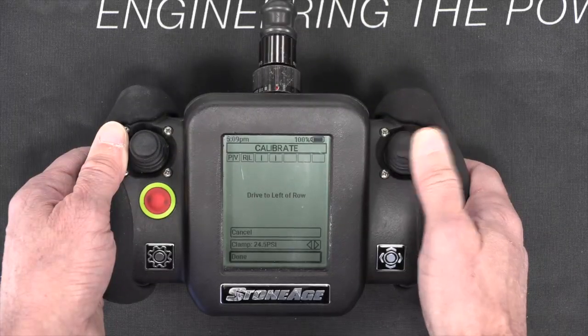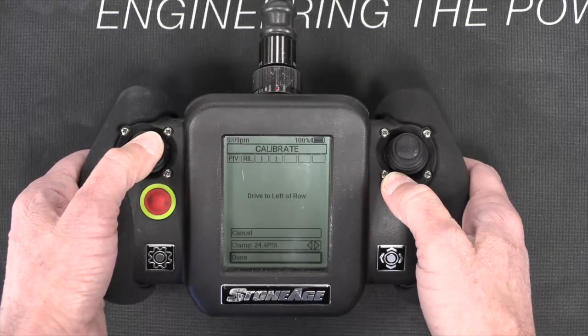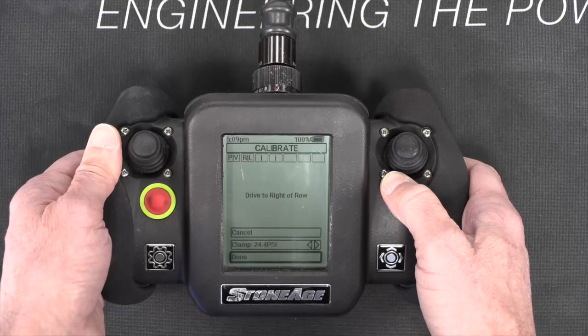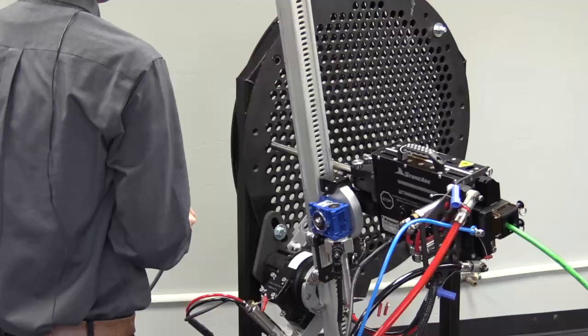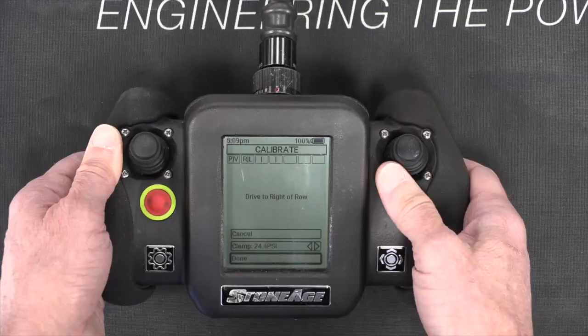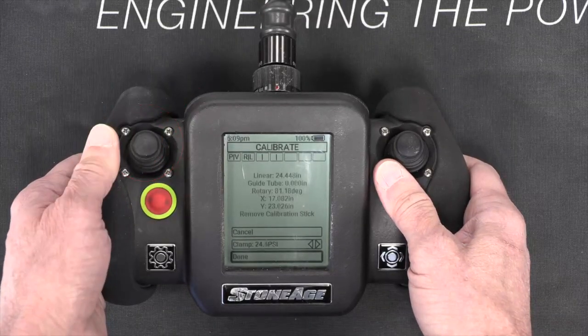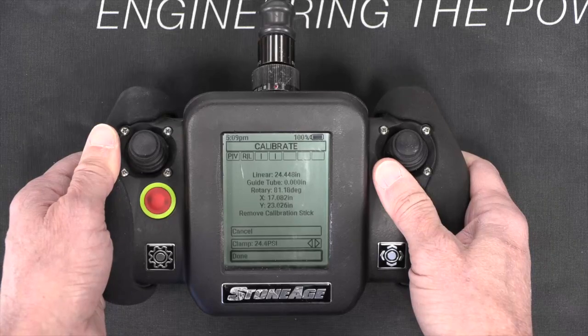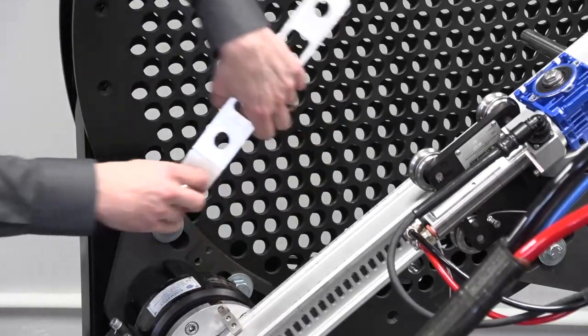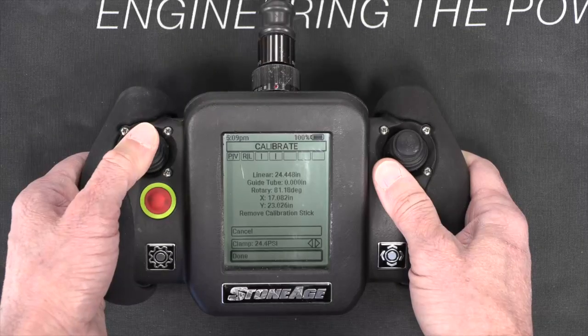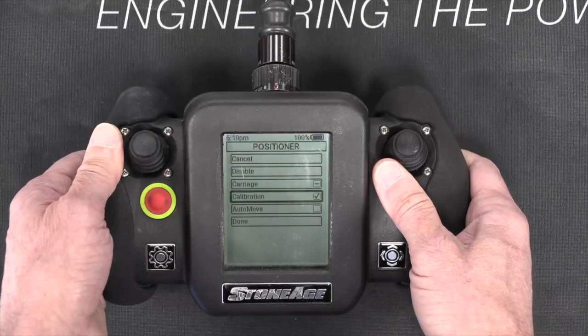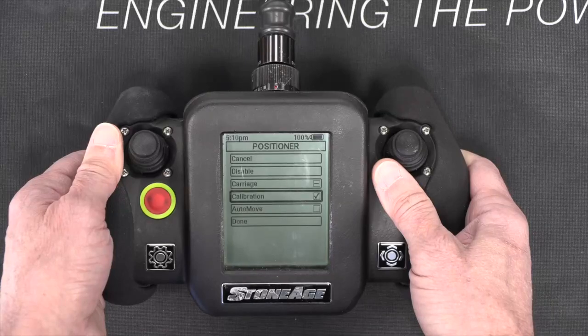Once you are positioned on a tube at the far left of the tube sheet, click Done. Now drive to the farthest tube on the right in the same row and click Done. The calibration is now complete and you will see the calibration values on screen. The display will instruct you to remove the calibration stick. The remainder of the job setup is identical to the procedure for a 3L system on a lightweight positioner.